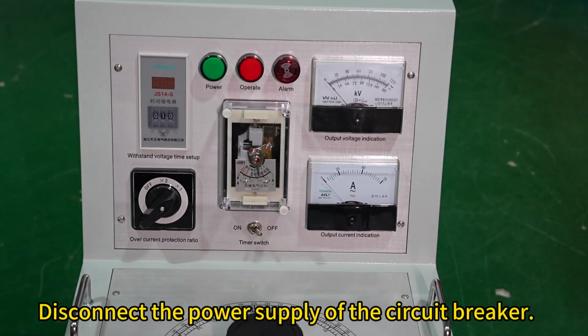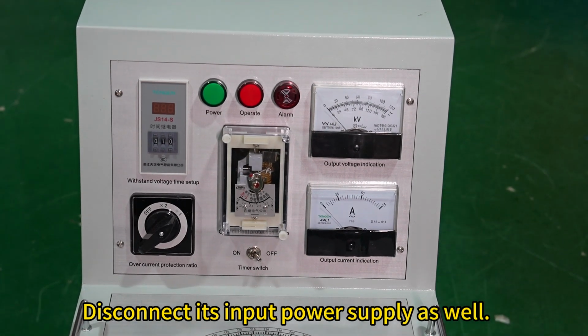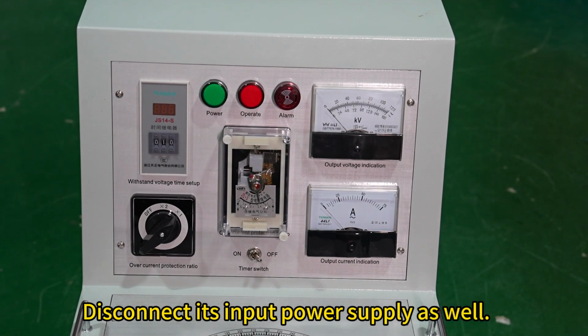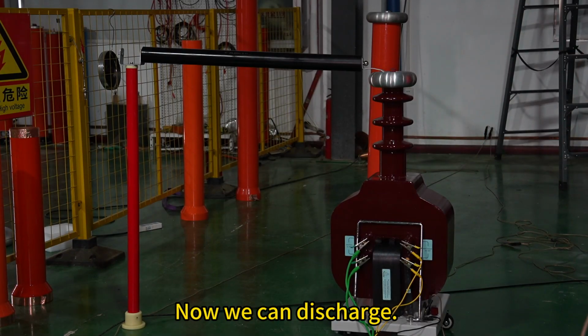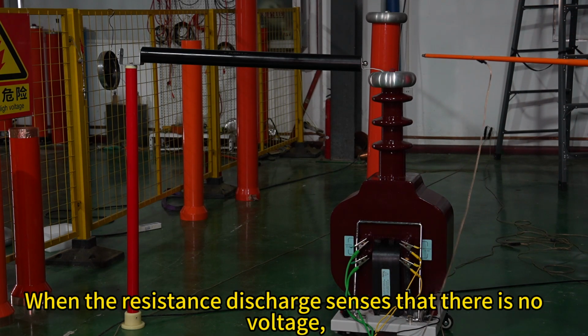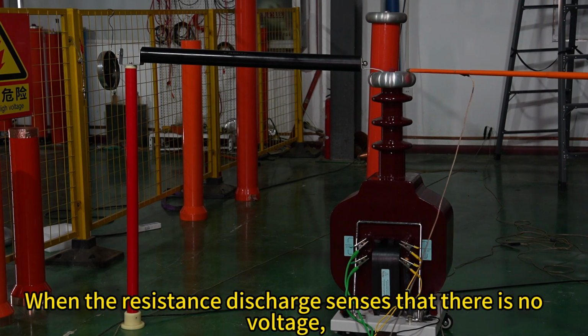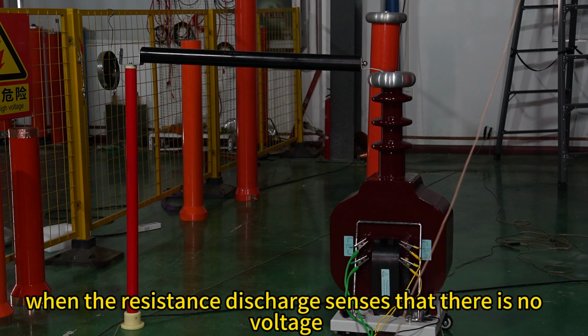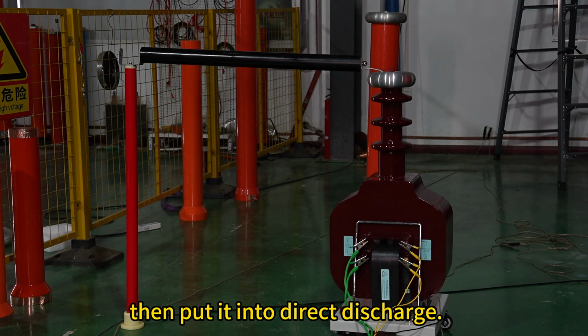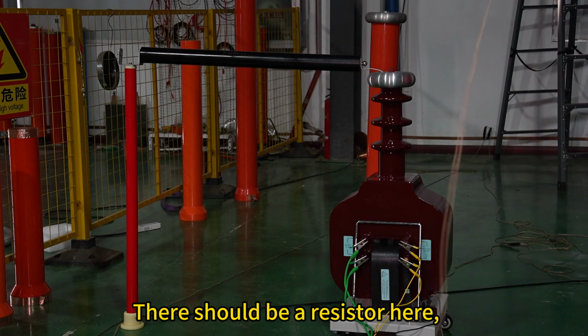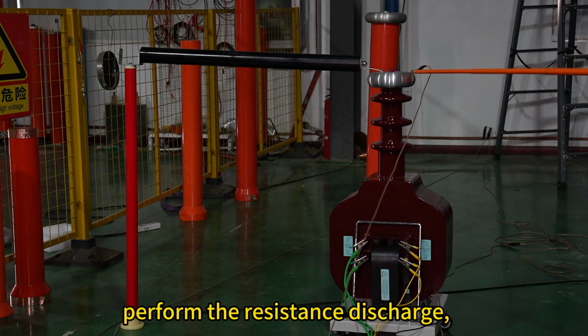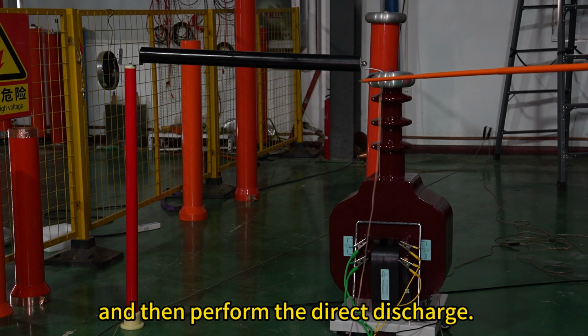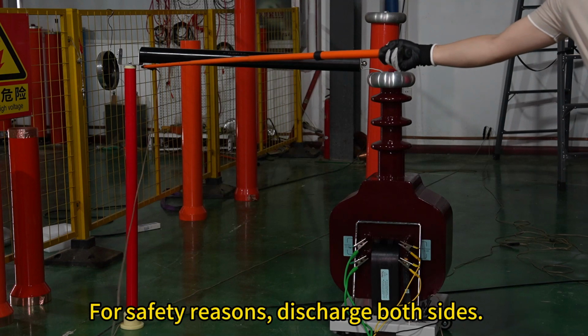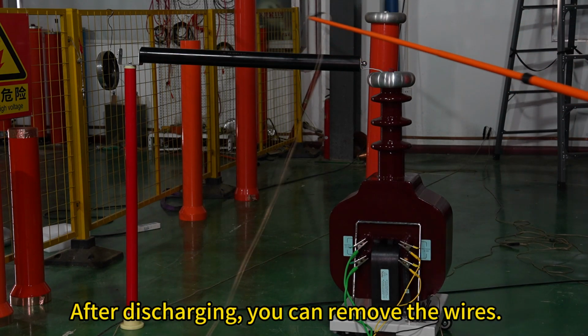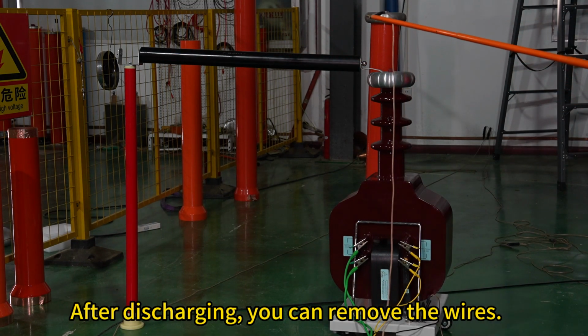Disconnect the power supply of the circuit breaker. Disconnect its input power supply as well. Now we can discharge. When discharging, perform the resistance discharge first. When the resistance discharge senses that there is no voltage, then put it into direct discharge. There should be a resistor here, perform the resistance discharge, and then perform the direct discharge. For safety reasons, discharge both sides. After discharging, you can remove the wires.